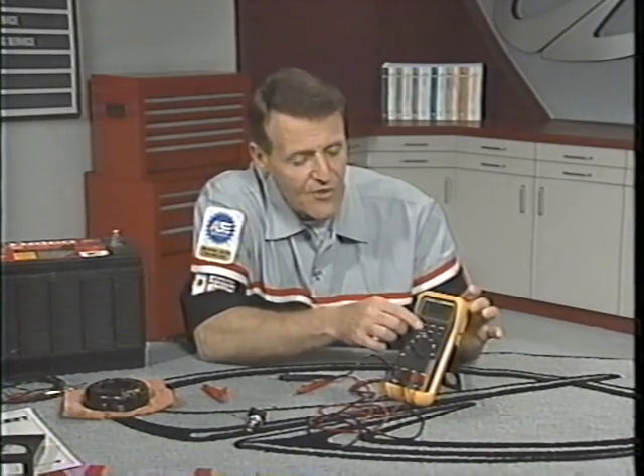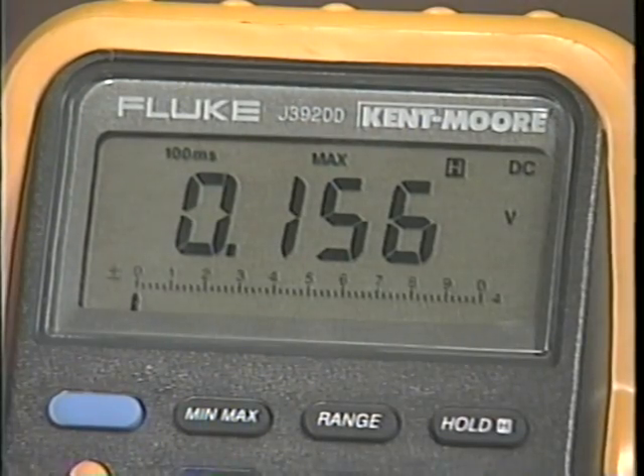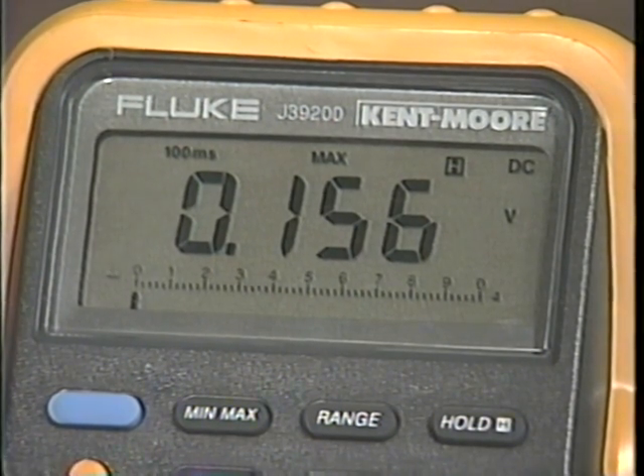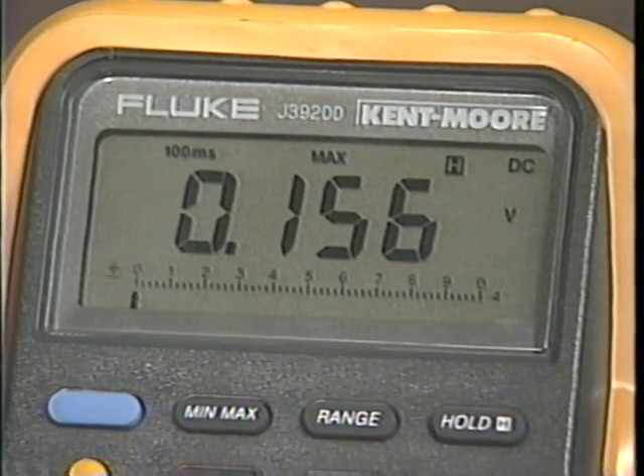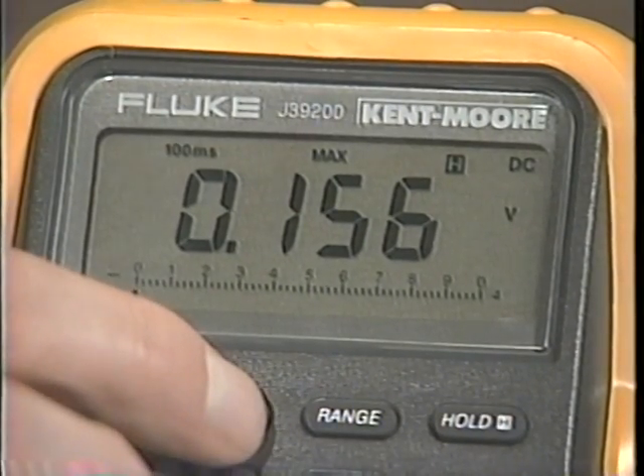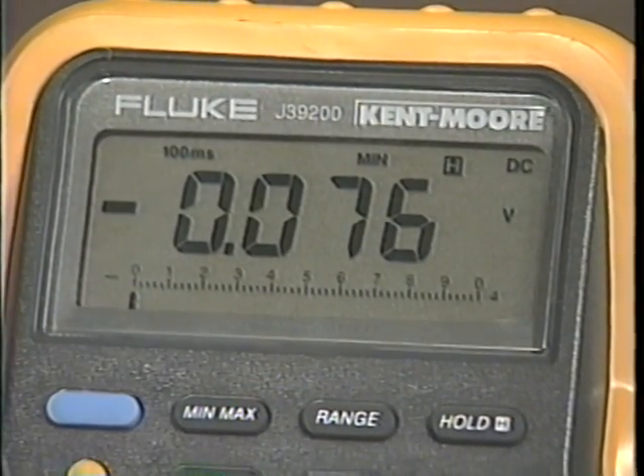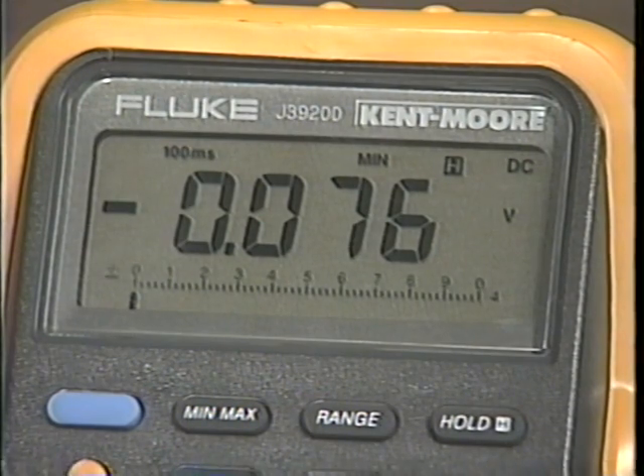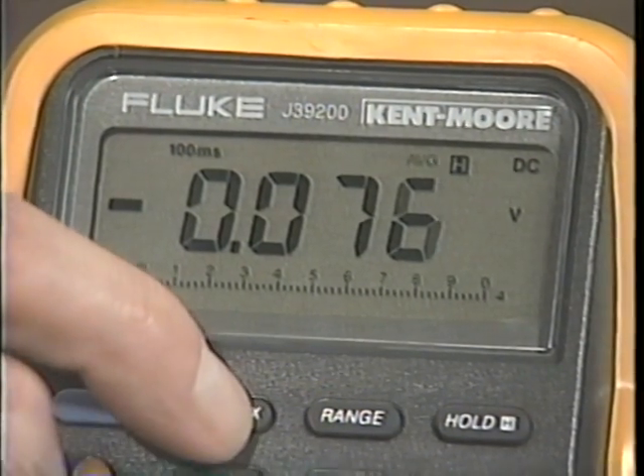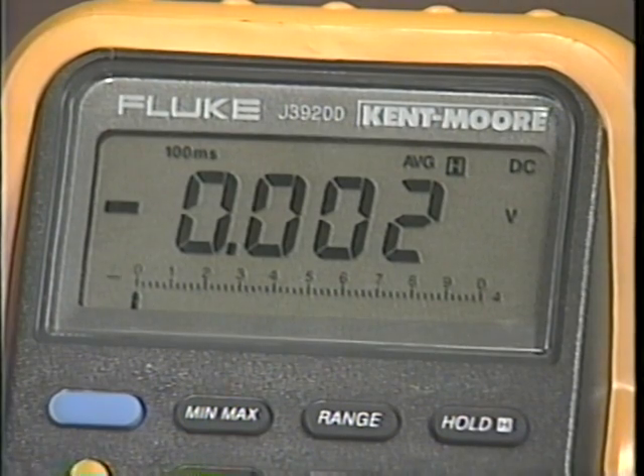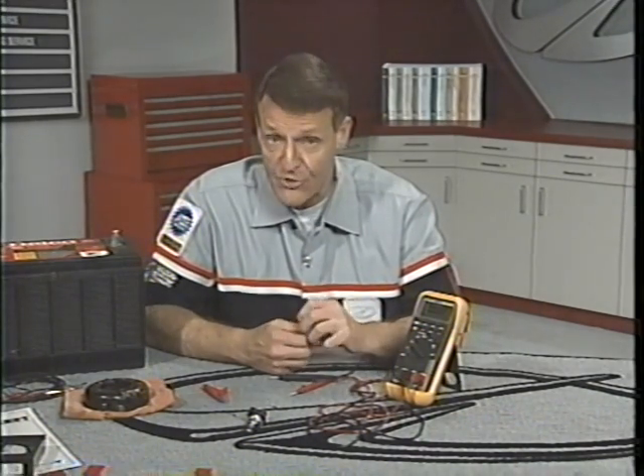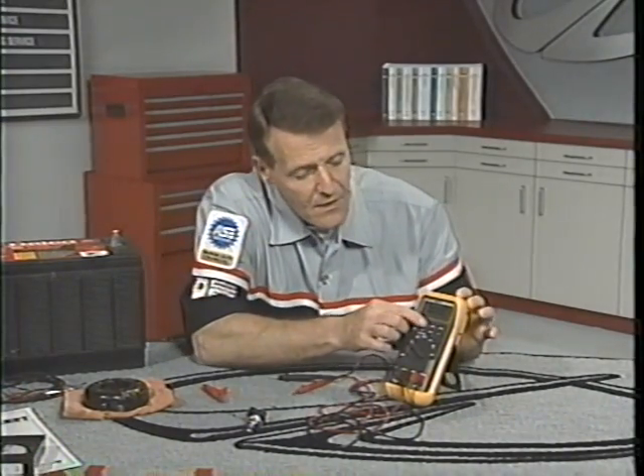Now we can play back the results. Pressing MinMax the first time displays the maximum reading recorded, 156 millivolts. Pressing it again displays the minimum reading of minus 76 millivolts. And pressing it a third time displays the average reading of minus 2 millivolts. At this point, you can either press hold to resume MinMax recording or press MinMax to exit from MinMax.